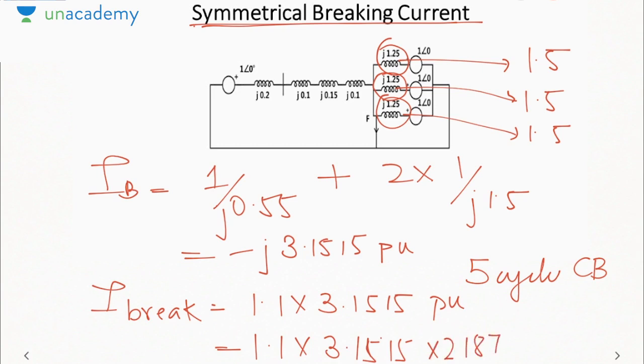So how much will this come out to be? 7581 ampere. Okay, so that is how you calculate the symmetrical breaking current of a circuit breaker. First, replace the subtransient reactance of motor by transient reactance, calculate the symmetrical current, and then multiply it by a factor corresponding to the speed of operation of circuit breaker.